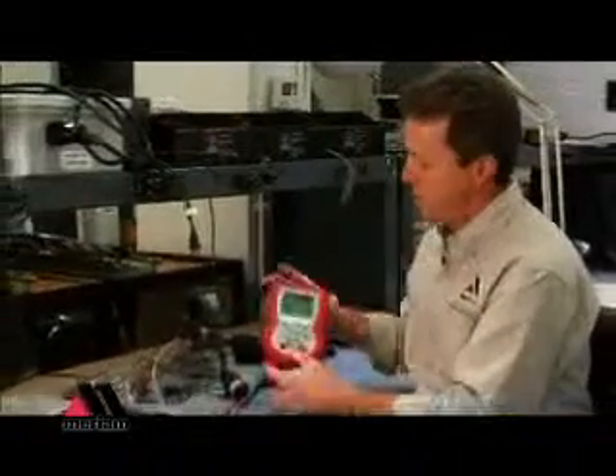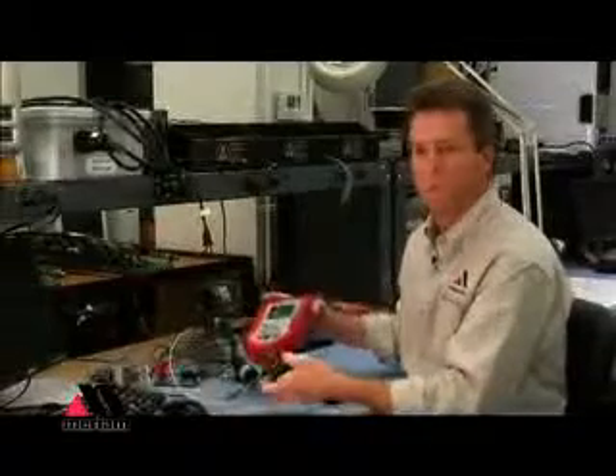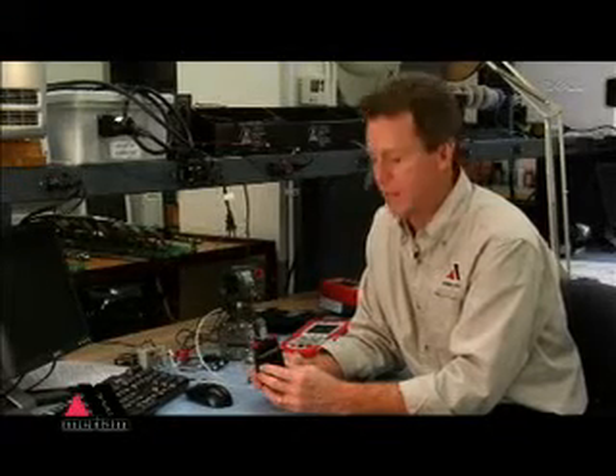Our electrical module is called a VMA, and even though the base unit has a built-in volt and current meter, it measures only. The VMA module will also provide DC volts or DC current to the user. So it will measure 0 to 55 volts or plus or minus 100 milliamps, or it will source 24 volts for powering up transmitters temporarily, or you can source precise voltages or currents for whatever needs that you have, whether that's calibrating a loop or checking a receiving device.